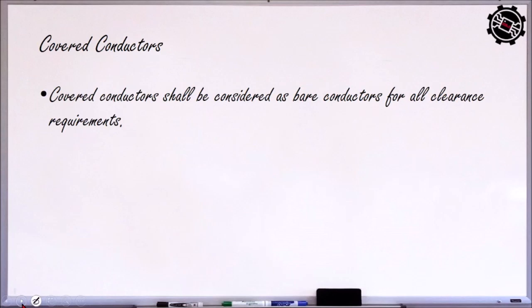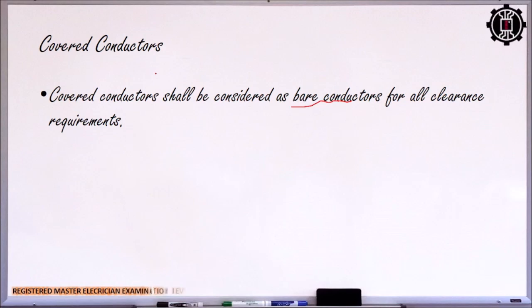So covered conductors. So covered conductors shall be considered as bare conductors for all clearances. So meaning yung covered conductors are not considered exempted, no, on the minimum clearance. So dapat they will still follow the 4.8 requirements, no, or the 2.7 requirements. So ano yung pinagkaiba ng insulated at covered? So dati discuss natin yung insulated, yung mismong insulation is part of the cable. So mayroon siyang sheath, mayroon siyang shield, mayroon siyang insulating material, saka na yung conductor. Sa covered naman, that is a bare conductor na nilagyan na natin ng covering. Na yung covering is not integral or not part of the conductor itself.